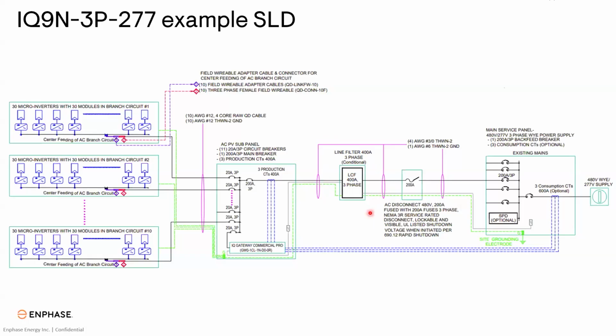The other scenario where you would need a line filter is if you have more than one gateway on a site. If you remember, I mentioned you can have up to 300 microinverters per gateway, but you can have multiple gateways on a site. So if you have two gateways on a site, you need one line filter. If you have three gateways on a site, you need two line filters. Every additional gateway you have, you need to add a line filter, essentially so those domains are kept separate and the gateways do not crosstalk.